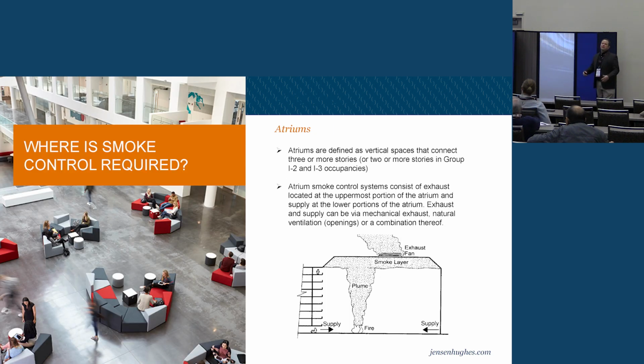Atriums are probably the second biggest application of where we're going to see smoke control. Again, this definition varies a little bit too, but it's any vertical space that's open that connects 3 or more floors. Some jurisdictions do 2 or more. For the most part, it's 3 or more. If it's an institutional occupancy, you're likely at 2 or more floors. Why the difference? Well, we may have people that can't self-evacuate.